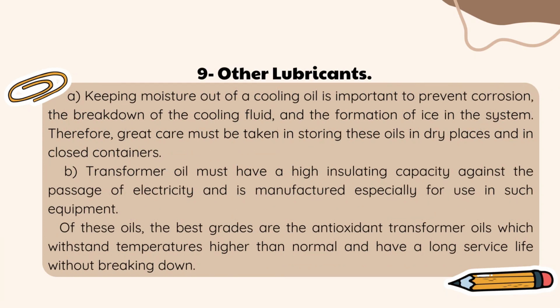9. Other lubricants. A. Keeping moisture out of a cooling oil is important to prevent corrosion, the breakdown of the cooling fluid, and the formation of ice in the system. Therefore, great care must be taken in storing these oils in dry places in enclosed containers. B. Transformer oil must have a high insulating capacity against the passage of electricity and is manufactured especially for use in such equipment. Of these oils, the best grades are the antioxidant transformer oils, which withstand temperatures higher than normal and have a long service life without breaking down.